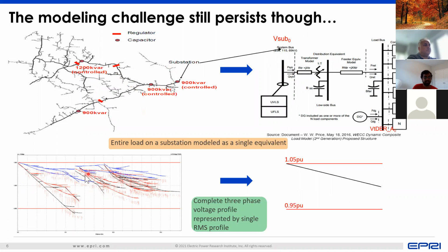There can be a variation in voltage across the feeder, as you see here, where this is a substation, and each node in the feeder can have a different variation of voltage profile across the entire network. And all of that needs to be represented by the simplistic model, wherein your substation is still represented, but now you have to combine all of the elements here into just these few elements that we have.